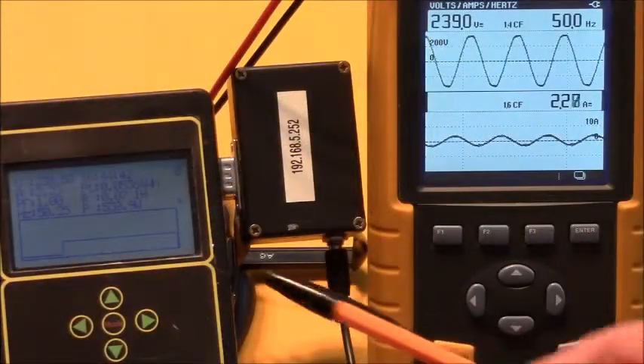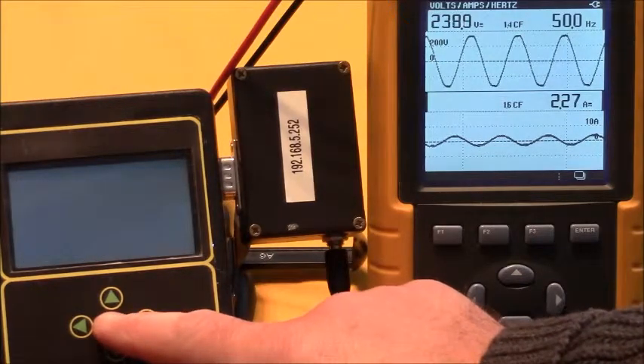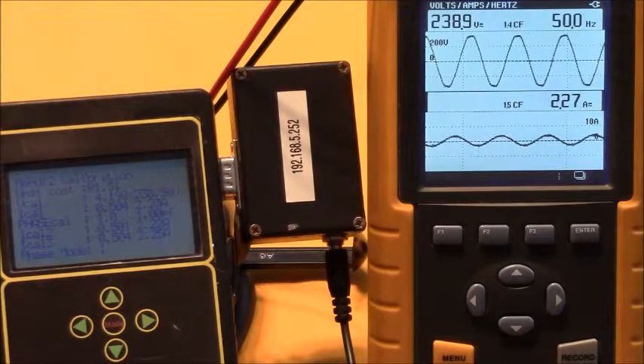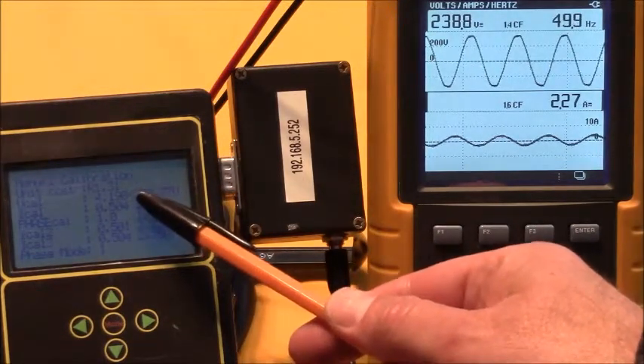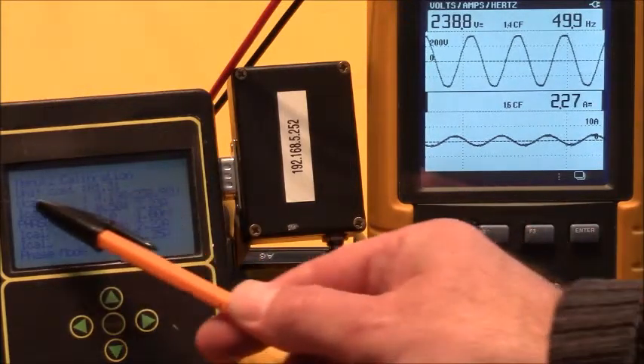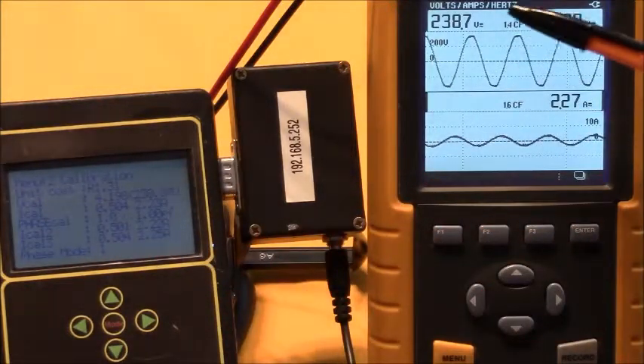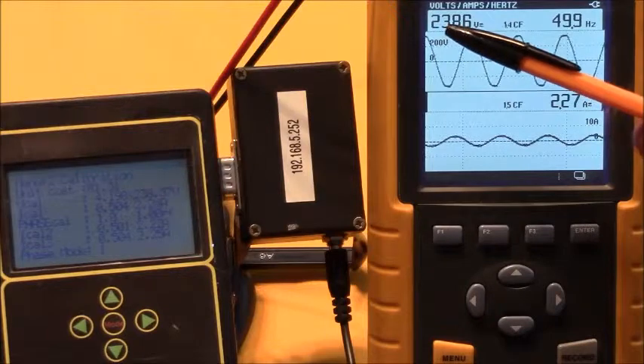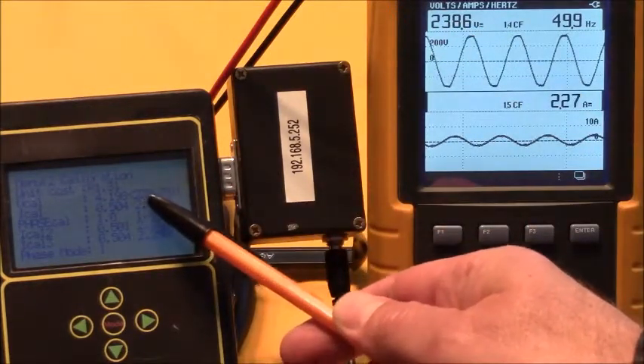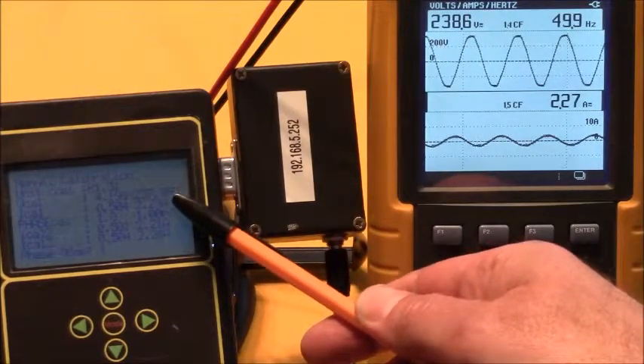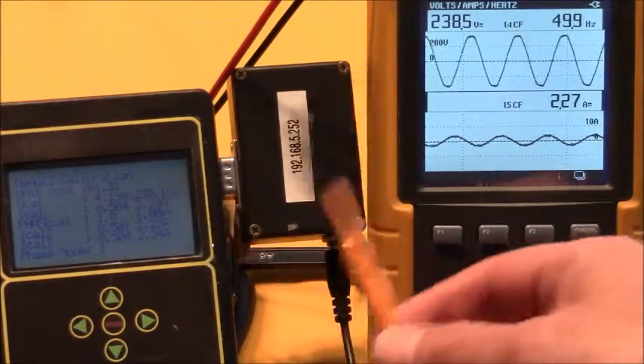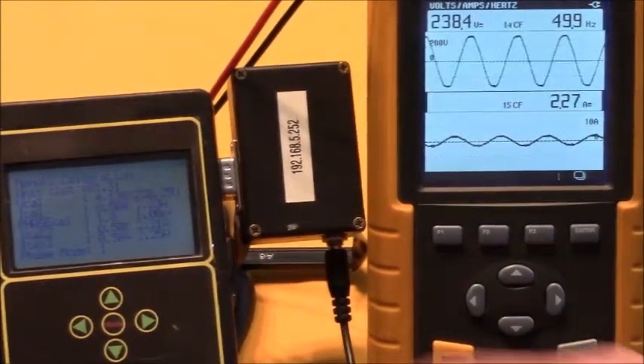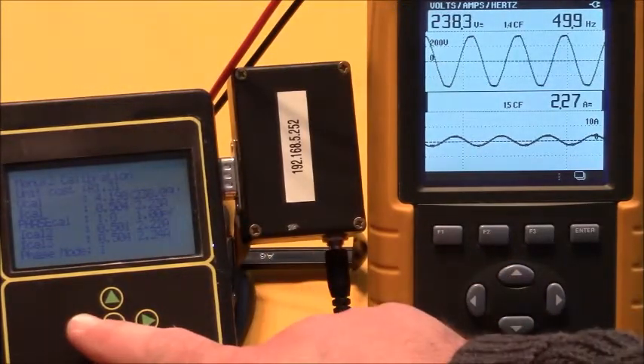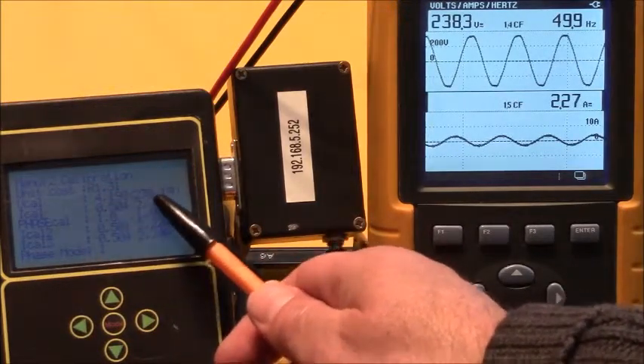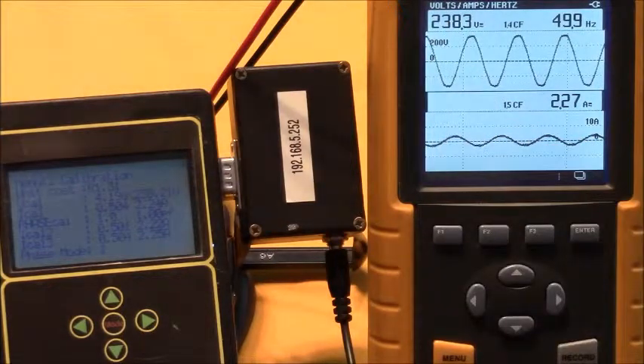Okay, going into calibration mode, the first thing you have to do is go to the calibration screen. Here's the calibration screen. Just a reminder, the little arrow shows you the one alongside the value that you're going to calibrate. So first of all, we're going to calibrate the voltage, and we've got the Fluke hooked up to the AC mains, and it's showing 238.6, and this is showing 238.48. It's roughly the same. We're very close. We're definitely within 1%, so that's okay. If we weren't, you would use the left right arrows to change this offset value so that that value would match your desk voltage measurement value.